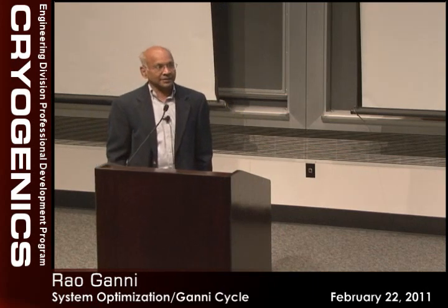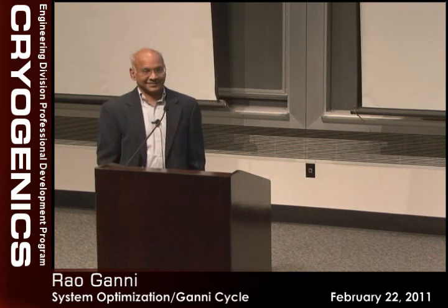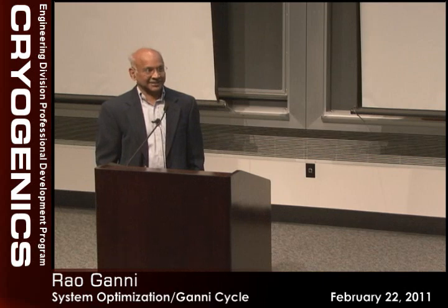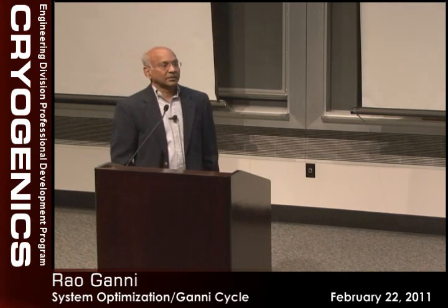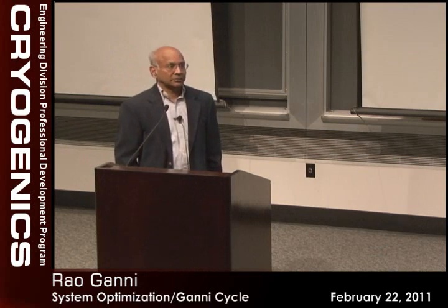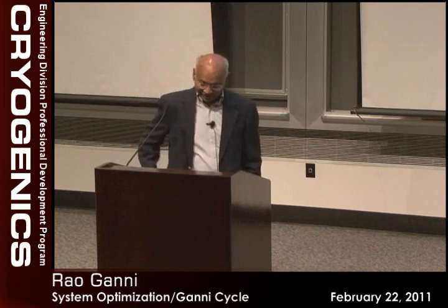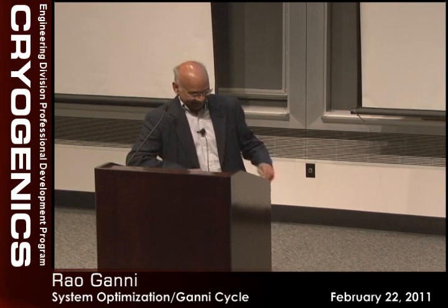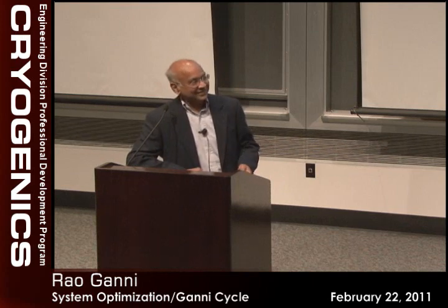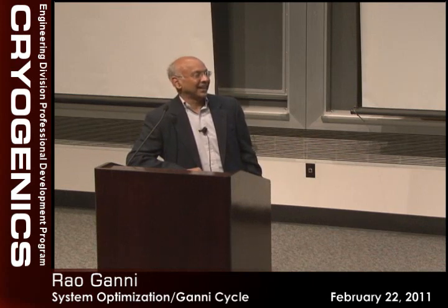I used to struggle with the technicians. Hey, don't change the set points. Don't fight the plant. Let it go. And that has gained a lot. We used to crash it every week. I know. And that was $60,000 to rebuild it. I just wanted to make that point.